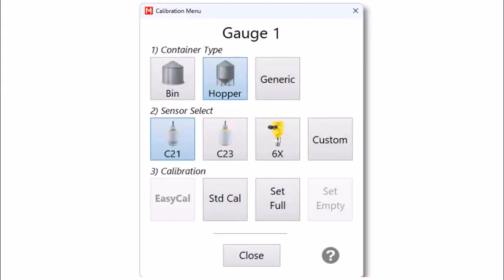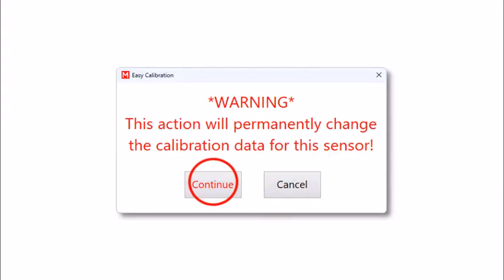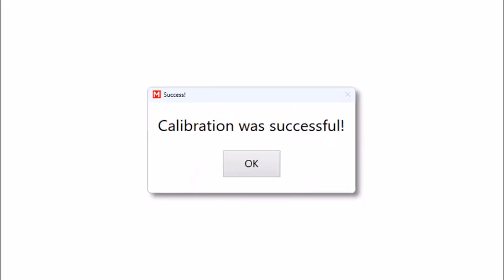Notice that the Set Empty button is not available for the hopper-style bin. This is because of how the signal can bounce off the angle of the cone when there is no grain present. Using the Set Empty button for a hopper-style bin could result in calibration errors. Set Full can be used for a hopper-style bin in the same manner as the standard bin. Simply click on the Set Full button, acknowledge the pop-up, and your adjustment will be automatically completed.